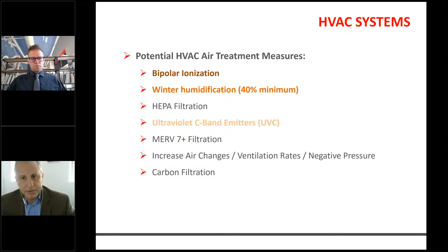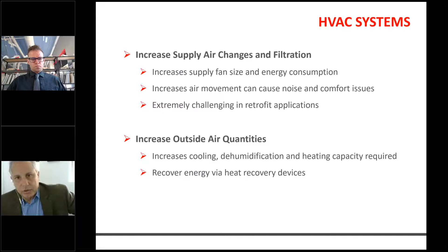The supply fan capacity, size, and energy consumption can be barriers. The increased air movement in a space, noise, and comfort issues as well can be challenges. And then for retrofits, it's tough to implement these systems or size without a lot of excess capacity oftentimes to allow this to happen. Outside air quantities can be increased when the weather allows for that. Otherwise, there are challenges trying to cool, dehumidify, and heat the air properly. And then incorporating energy recovery devices after the fact can be challenging as well.